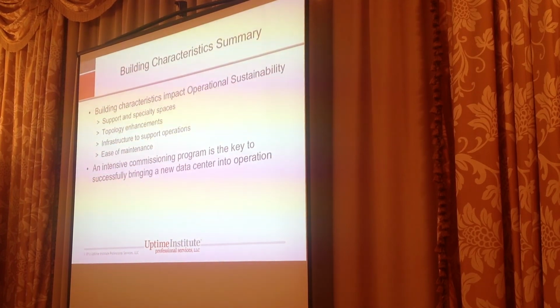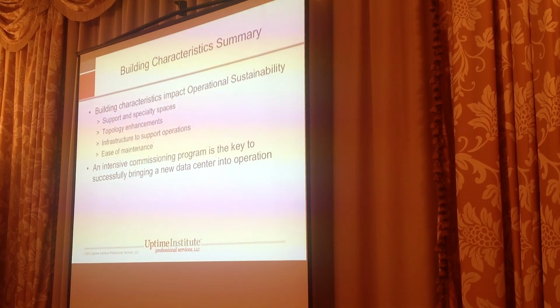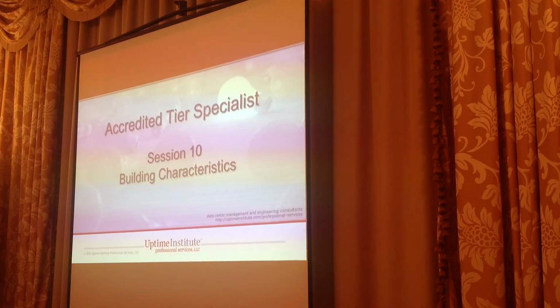So in summary, you need to have those support and specialty spaces. Topology and enhancements are good to have - yes, you may only have a fault-tolerant electrical system in your tier 3, but it's a good thing to have. It's important for ease of maintenance, to have the infrastructure to support other things. And we can't stress enough the importance of commissioning - have an intensive commissioning program, because what you're going to do is find problems and break those pieces of equipment up front, getting all the bugs out before you go operational with your computer equipment.